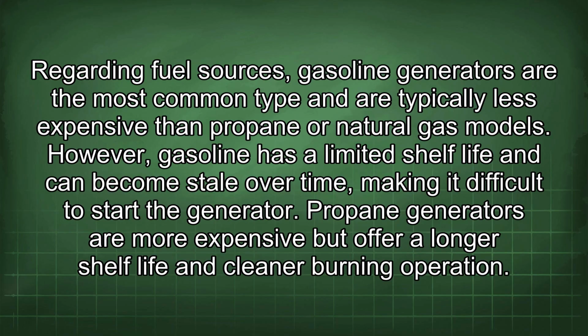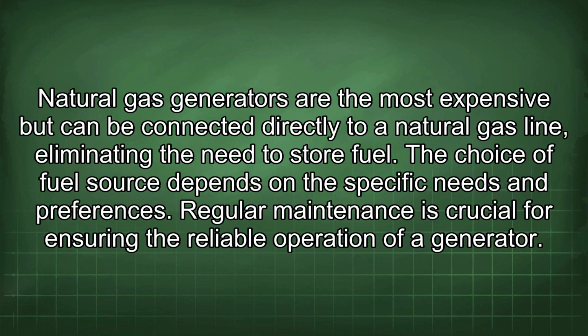Regarding fuel sources, gasoline generators are the most common type and are typically less expensive than propane or natural gas models. However, gasoline has a limited shelf life and can become stale over time, making it difficult to start the generator. Propane generators are more expensive but offer a longer shelf life and cleaner burning operation. Natural gas generators are the most expensive but can be connected directly to a natural gas line, eliminating the need to store fuel. The choice of fuel source depends on the specific needs and preferences.